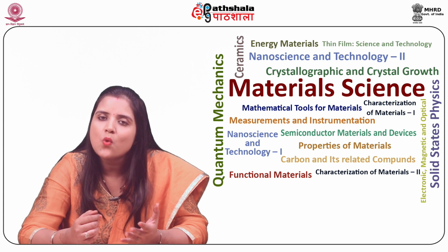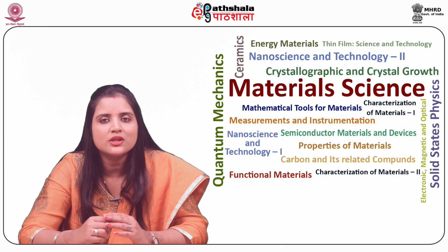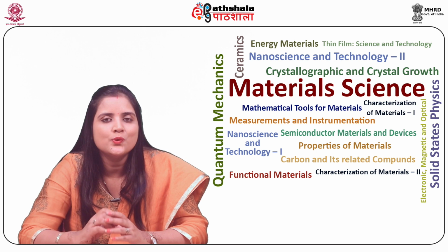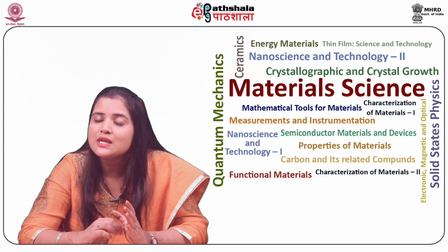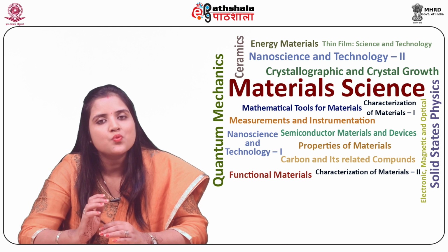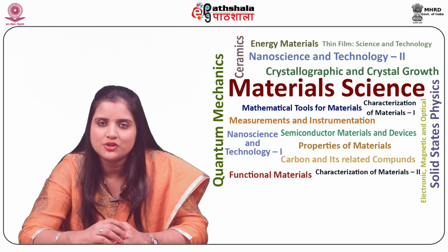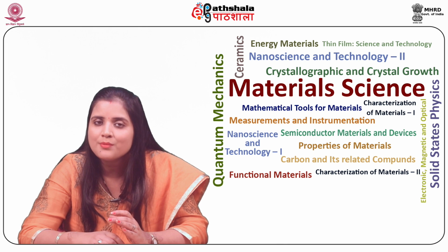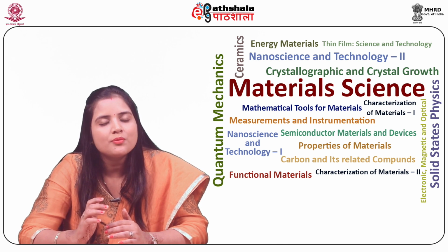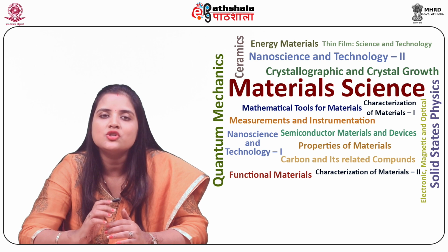Spectra are acquired by rotation of gratings, which contain 1200 grooves per mm and are placed at 330 nanometer excitation at 500 nanometer emission. To overcome oxidation of the grating, it is coated with a protective layer of MgF2.